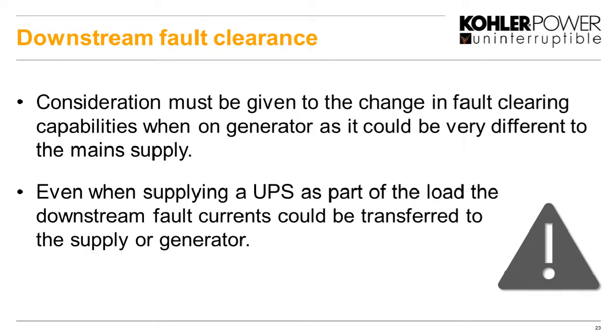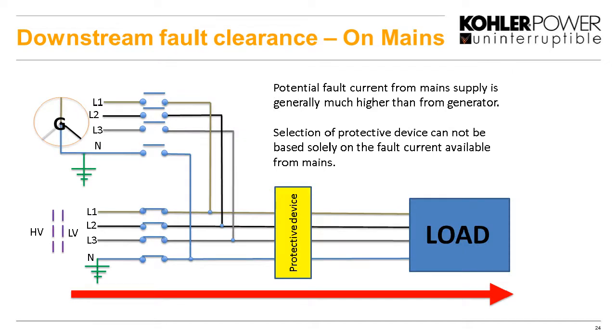When we're putting a generator in, we have to make sure we understand the downstream fault clearance. So we have to consider the fault capabilities, or fault clearing capabilities rather, of the generator, because these could be very different to the mains. And this is very important to consider, especially on installing a generator to an existing system. Okay? So even if you've got a UPS and that's the load or part of the load, the downstream fault currents could still be transferred to the supply or to the generator itself.